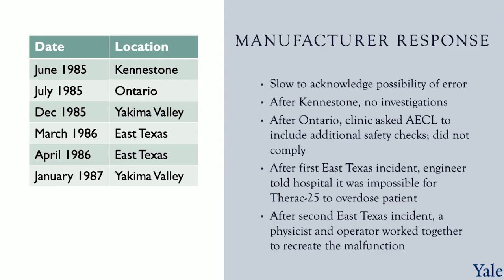Again, the malfunction 54 error appeared, and the operator heard the patient moaning for help in the treatment room. The patient described the feeling of fire on the side of his face where he was receiving treatment. After this incident, a physicist at the hospital began his own investigation. He worked with the operator and retraced all of her steps. Through lots of experimentation and button pressing, they discovered that a quick data entry edit from x-ray to electron mode could recreate this malfunction sequence and overdose. Without the effort of these two individuals, it may have taken much more time and many more incidents for the Therac-25 bug to be found.